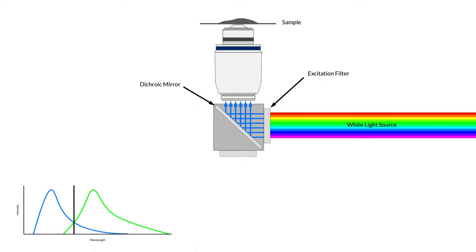In this example, the dichroic is designed to split at 500 nanometers, so everything shorter than 500 nanometers reflects at a 90 degree angle and goes into the objective, and everything longer than 500 nanometers transmits directly through. After this dichroic, our excitation light is focused by the objective onto our specimen. Our green fluorophore goes from a ground state to an excited state, relaxes for a brief period, then emits photons of light in their nominal emission range.